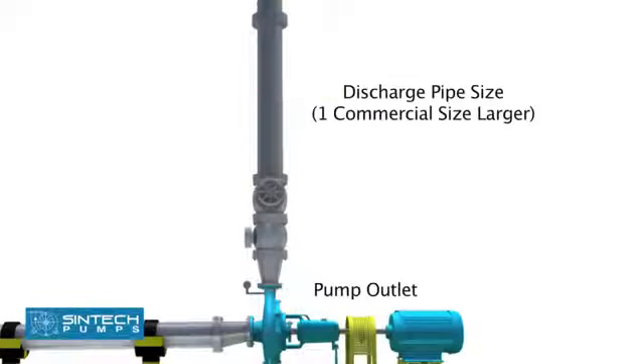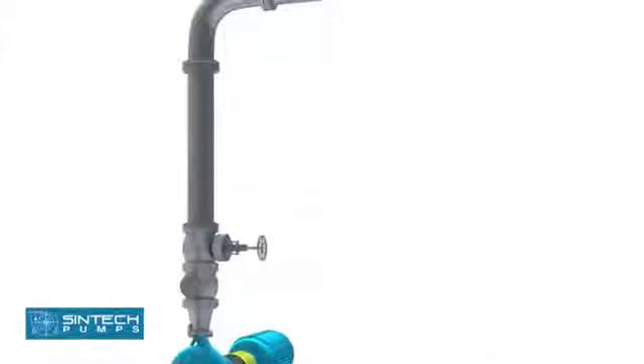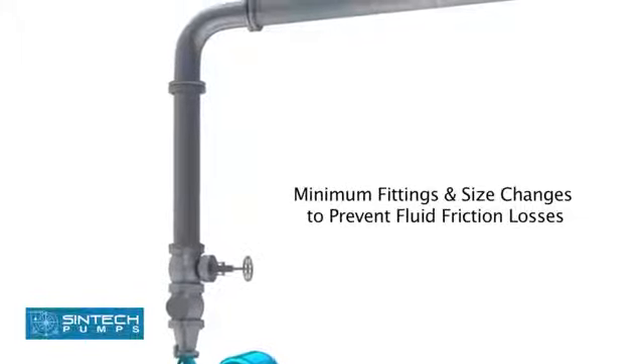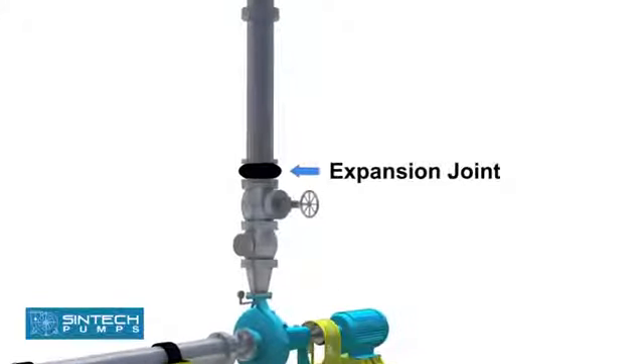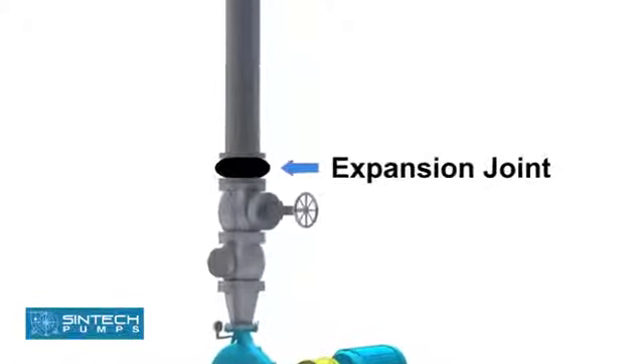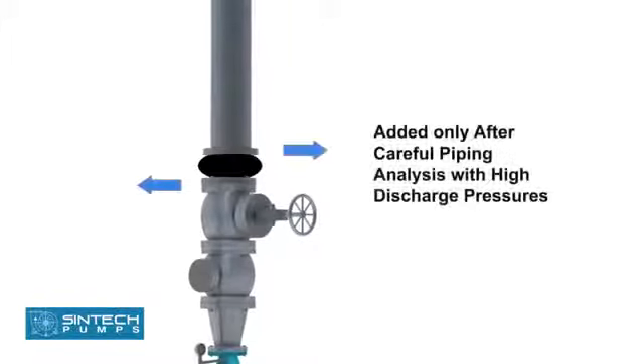Discharge pipe size should be at least one commercial size larger than the opening of the pump outlet. The number of fittings and size changes should be minimum to prevent fluid friction losses. Expansion joints may be used only after careful piping analysis, especially when discharge pressures are on the higher side.